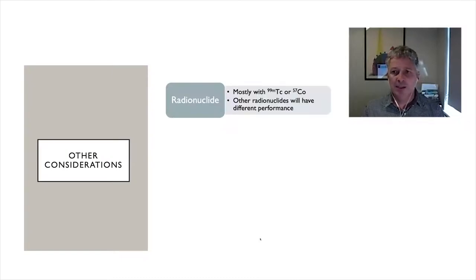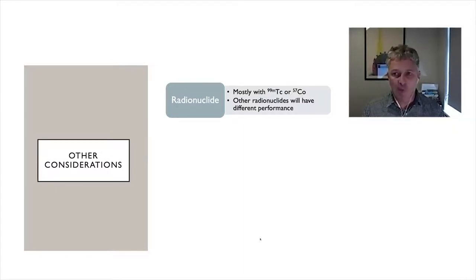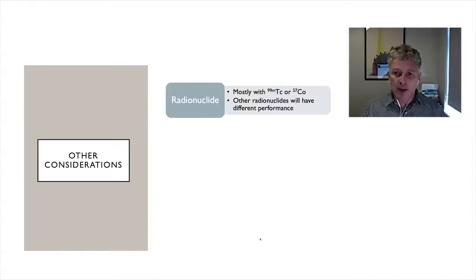Regarding radionuclide choice: most imaging is performed with technetium-99m, so we generally try to do most tests with technetium-99m. Sometimes cobalt-57 is used because it's more convenient and its emission properties are similar to technetium-99m. Other radionuclides will have different performance — for example, if imaging with iodine-123 or iodine-131, some measurements will change depending on the radionuclide used.